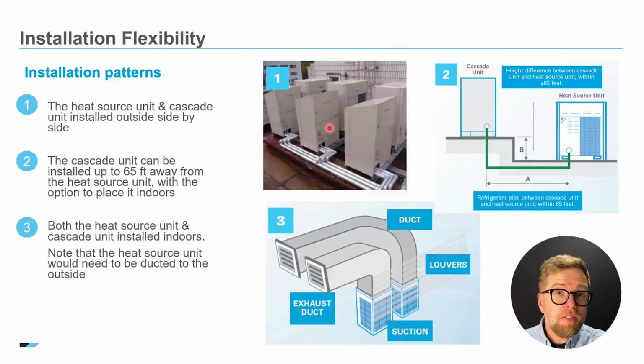For install, the outdoor heat source unit can be placed up to 65 feet away from the Cascade unit, which can either go inside or outside. And this potentially frees up a lot of space and opens up some design possibilities, especially in challenging sites.